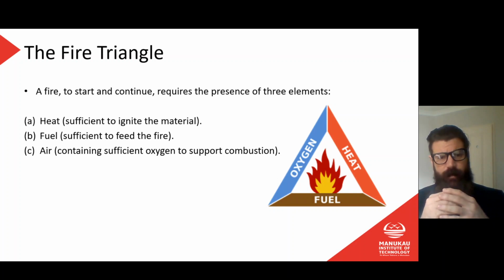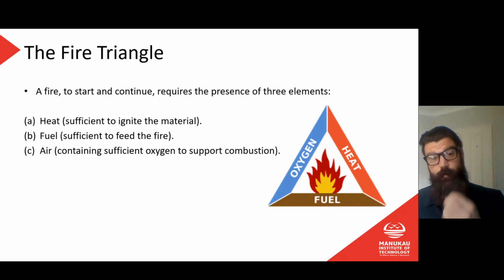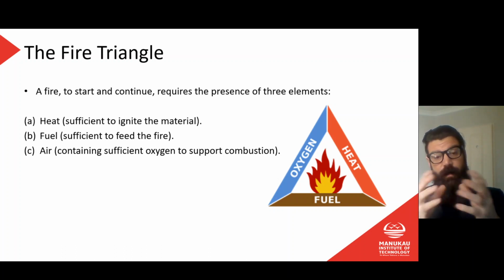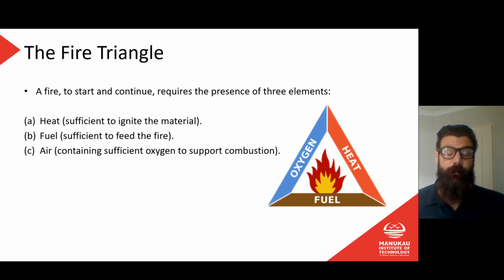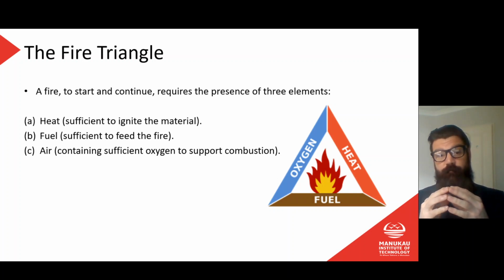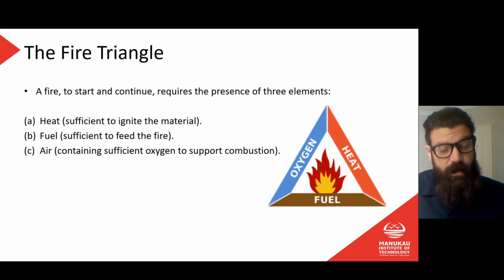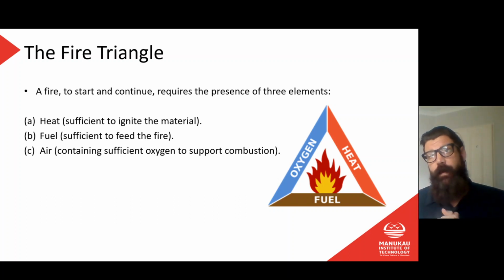And usually what happens is through that chemical reaction, oxygen binds with the molecules of whatever that is, causing a third compound to be created, and that's what we think of as ash or the carbon deposits or whatever that is left behind after a fire. So that's the interaction between oxygen and that material. Now, that interaction, at a chemical level, is going to be greatly increased by heat. The more heat we put into that oxygen and whatever it is reaction, then the faster that reaction will occur, and one of the byproducts of that reaction is then more heat, which continues the fire. Oxygen reacts with lots of things.